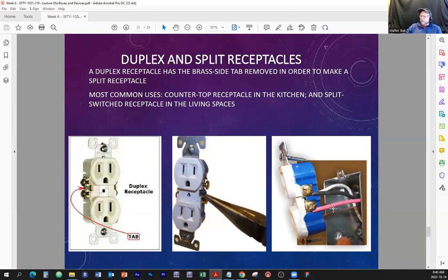You would use 14/3 cable or 12/3 or 10/3. You connect the neutral as it is to the neutral terminal. And you have the black wire, which is hot, which would connect to one circuit breaker. Because they're separated, you have another hot, connected to a separate circuit breaker. So you have two circuits.